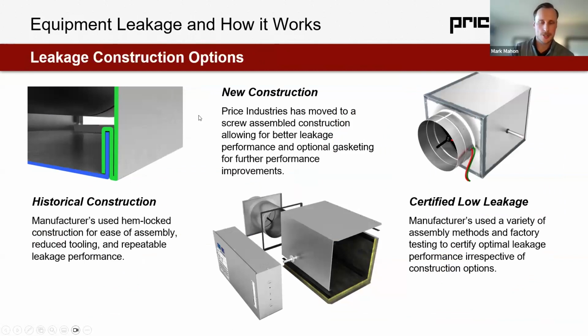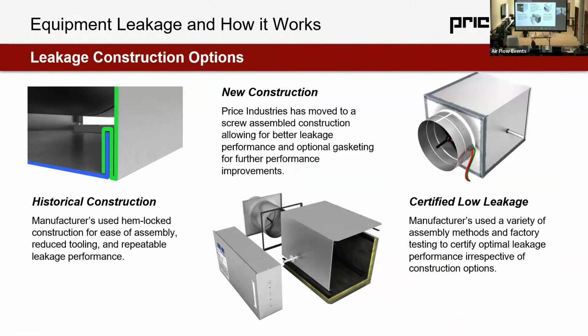To speak to leakage construction options in a little more detail, the historical construction that most manufacturers use is a hem-locked construction, very similar to a Pittsburgh lock, but it's not folded over twice. This hem-locked construction does have some additional mechanical mating to really squeeze that blue piece of sheet metal into the green piece of sheet metal. And this is a very repeatable performance.